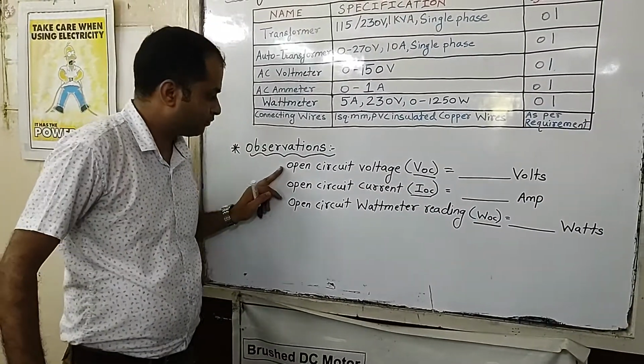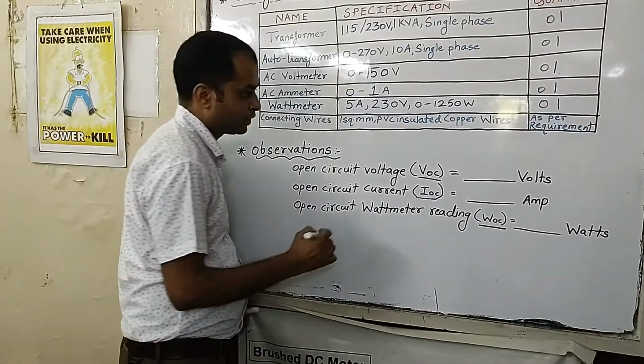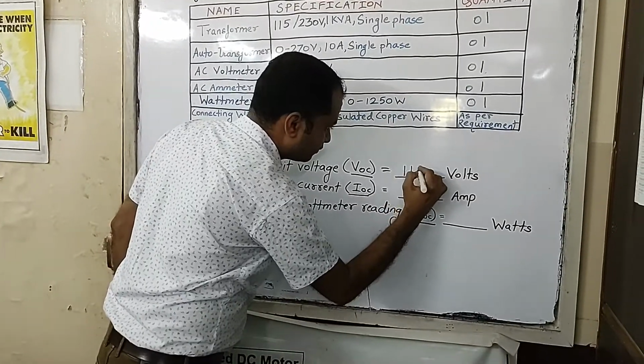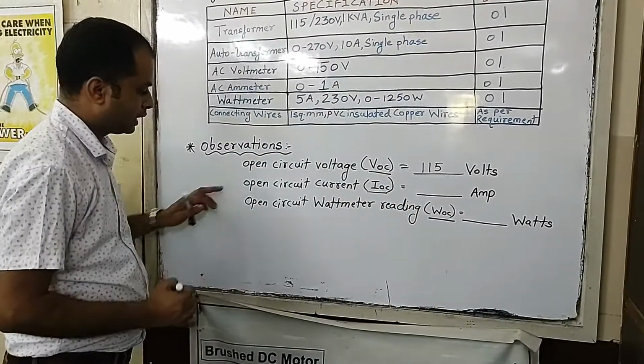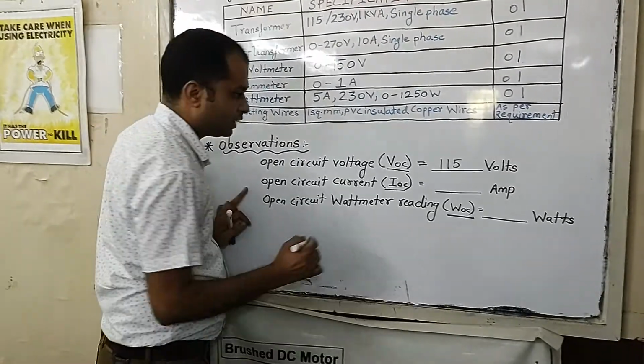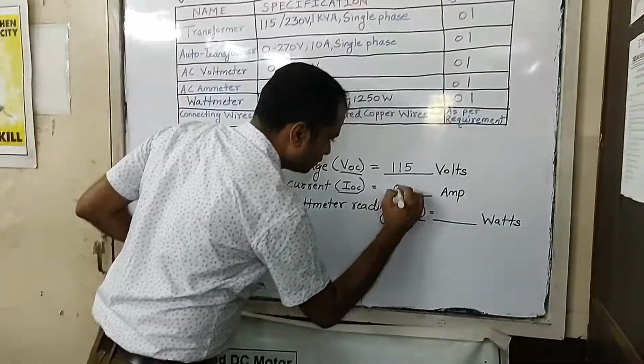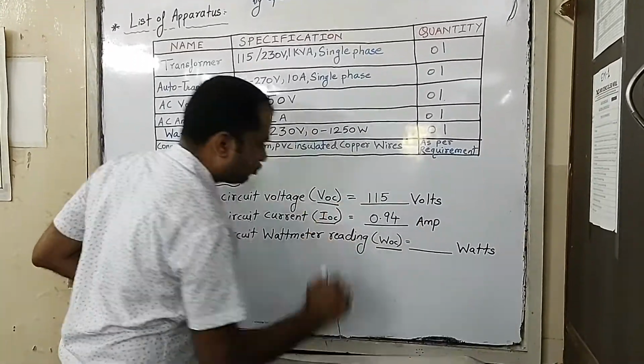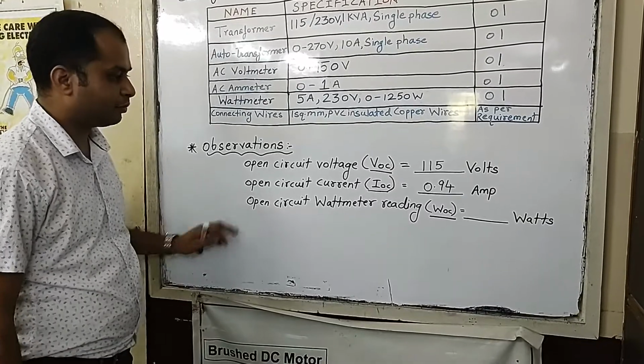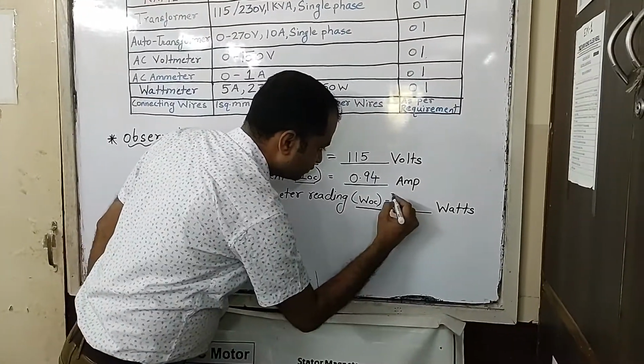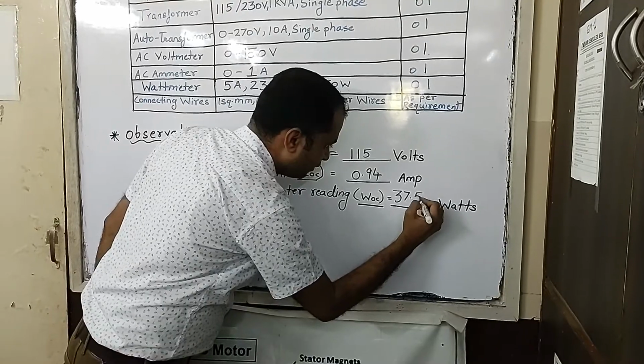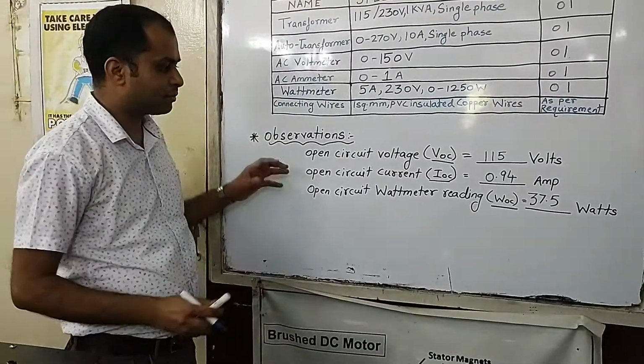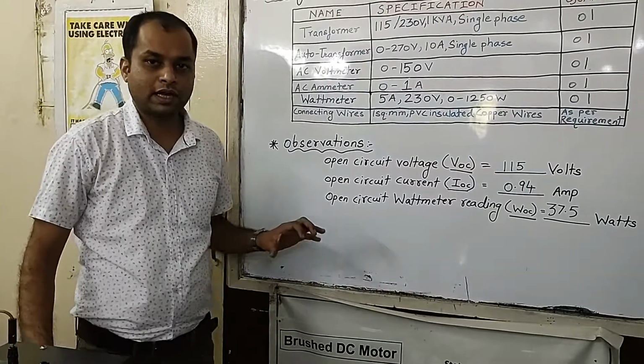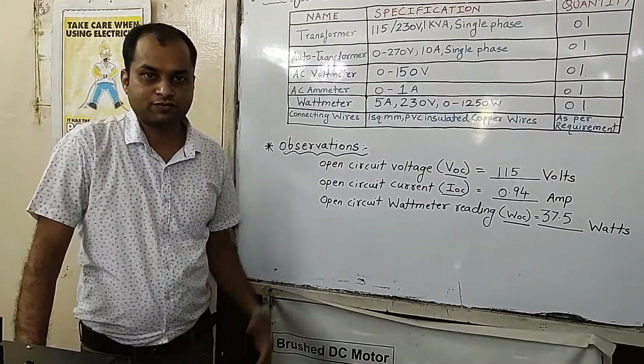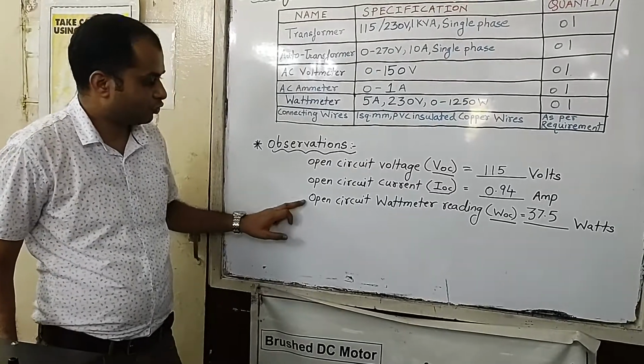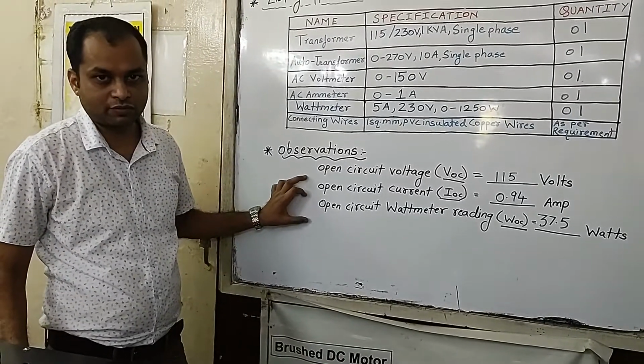As we have measured the open circuit primary voltage as 115 volt, we will note it down here. The open circuit primary winding current was 0.94 ampere, and the wattmeter reading that we got is 37.5 watts. This reading may show some difference, as we have already shared the readings for the different batches. So we have to note down these three readings as the observation in this experiment.